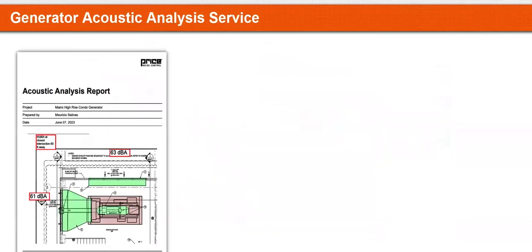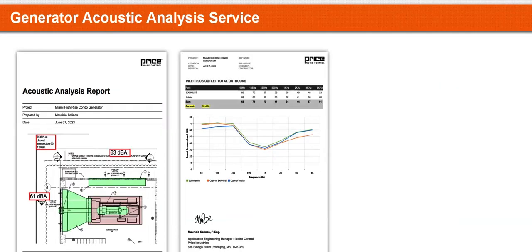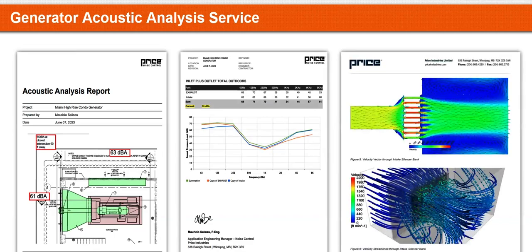You start seeing now a common approach on all these solutions. It starts by using accurate tested data, using the right calculations or reputable software to ensure that you can effectively size the length, width, and height of your silencers. You see the added service of really predicting what the impact on performance is going to be by adding silencers or barrier walls or acoustical panels in the way of airflow.